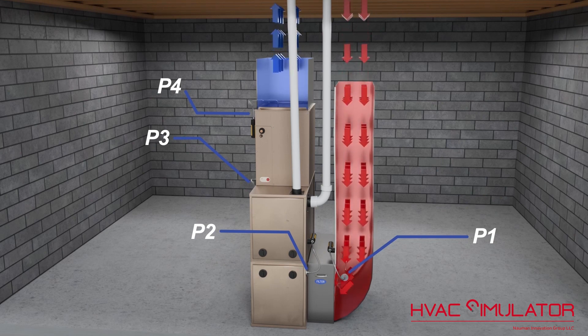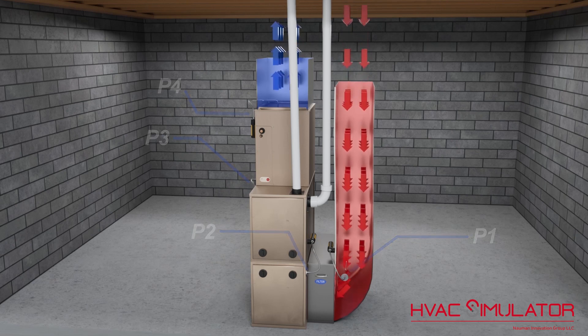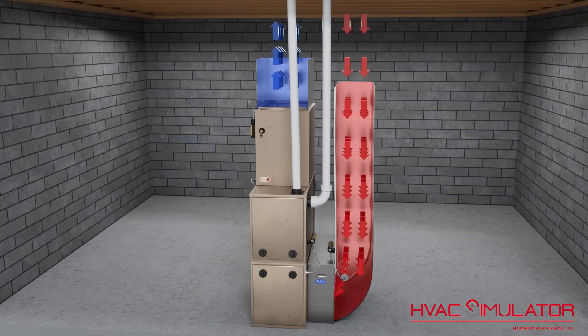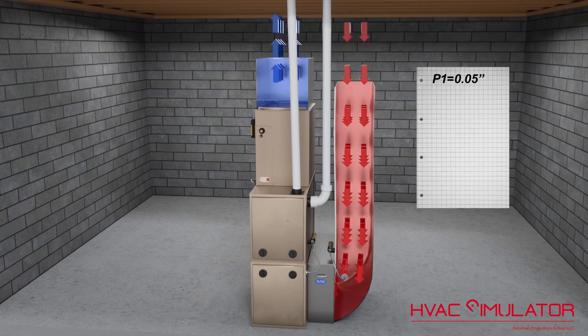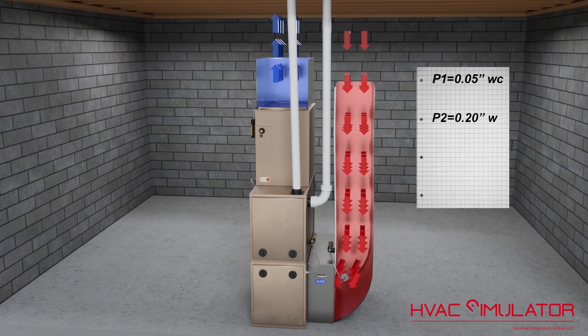Once the system runs at optimal blower speed, document the four heating and the four cooling speed pressures. These values can be referenced during a maintenance check and quickly determine a performance issue.